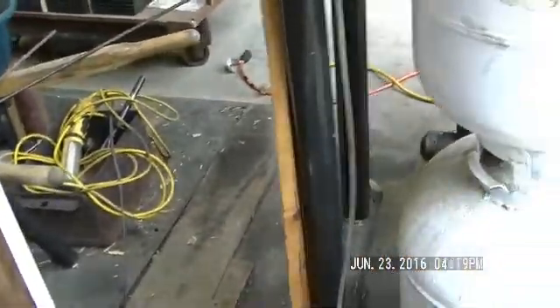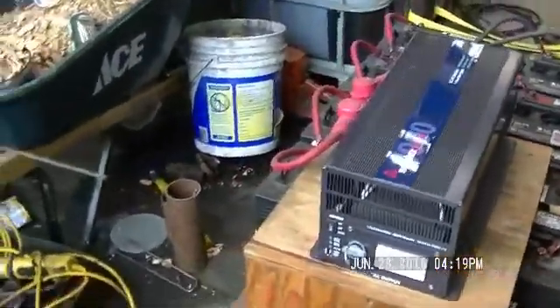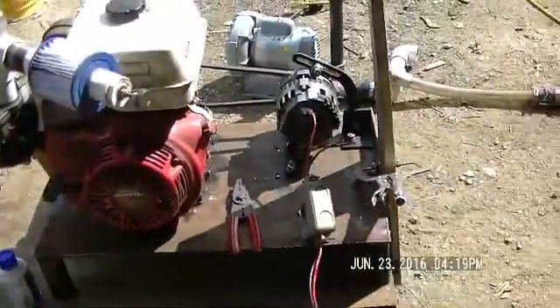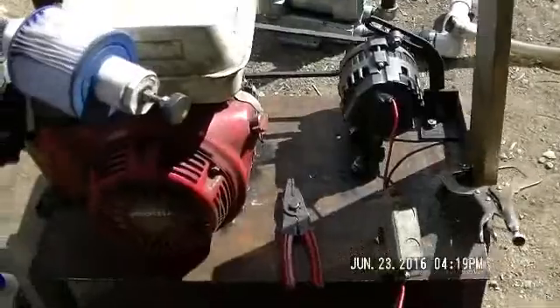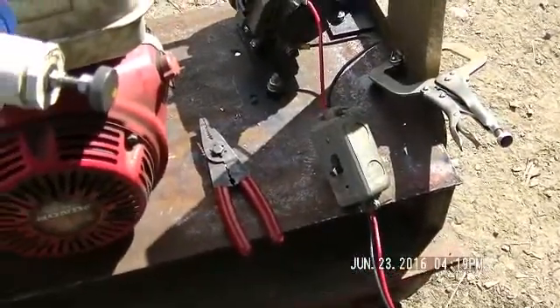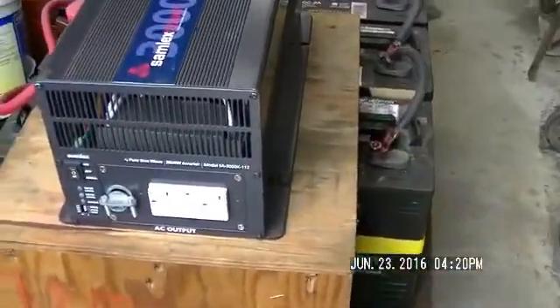Just like me, sometimes I don't work! So the first thing I'm going to do is go and turn on the inverter. Those batteries were fully charged about a week ago, so they've been just sitting. These wires here are coming from the alternator — a 100-amp alternator made for this thing; it'll take a lot of heat. I've got a shutoff switch so I don't put any power out until I'm all hooked up and ready, to avoid sparks. The order of the run-up is to start the primary blower, and we're going to do that right off of the inverter so we don't have to depend on anything else.